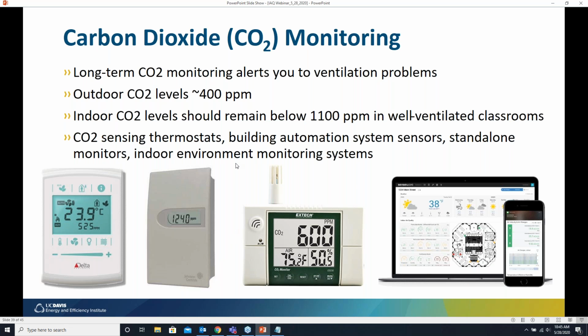Okay, so lastly, here I want to talk about CO2 monitoring. After you commission your ventilation systems and upgrade your filters, I really want to strongly urge you to consider CO2 monitoring for your classrooms. Long-term CO2 monitoring will alert you to ventilation problems. Indoor CO2 levels should remain below 1,100 parts per million in well-ventilated classrooms.